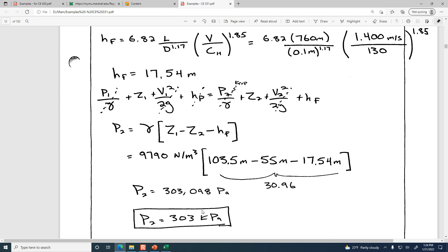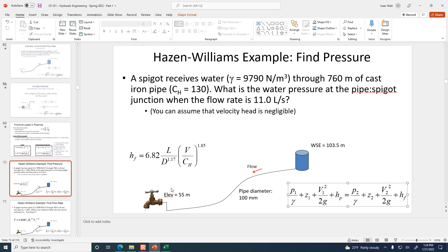Once the water exits the faucet it loses all that energy. The spigot regulates flow by moving a ball off a seal, increasing or decreasing an orifice inside the valve. If you only want 11 liters per second, you'd mostly close the valve so there's just a tiny orifice and all the remaining energy in the pipe is exerted as a local loss as the water flows through at that flow rate. Any questions about these calculations?